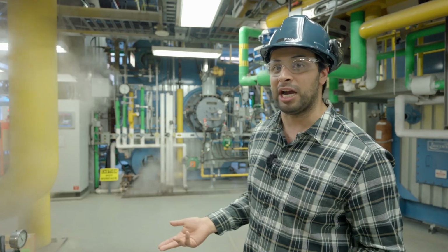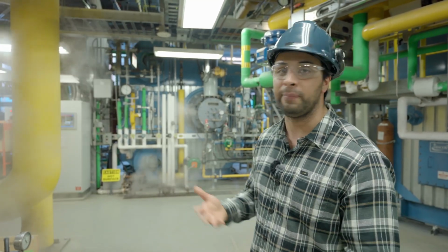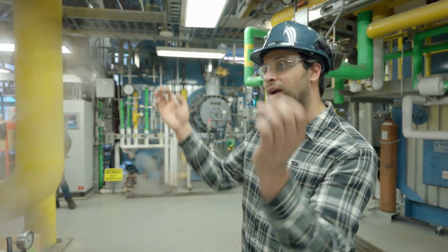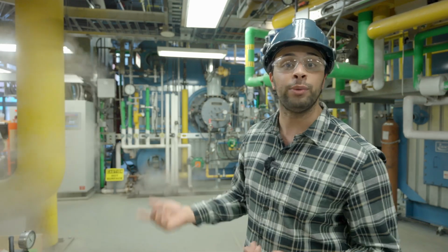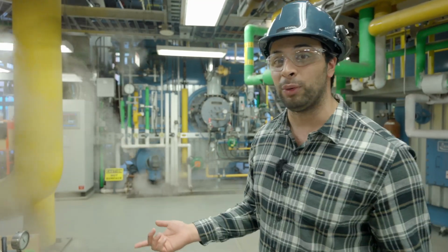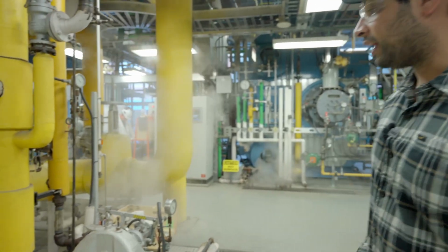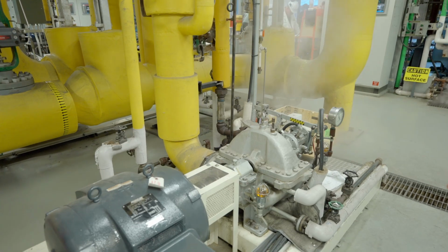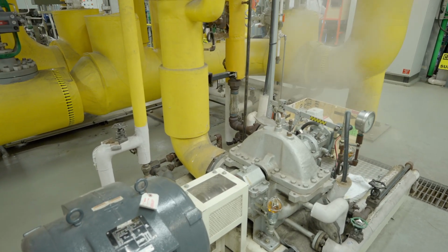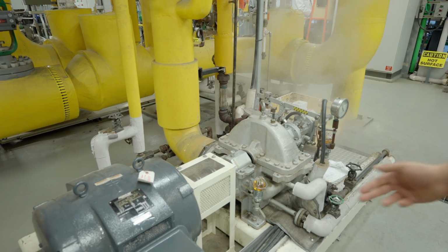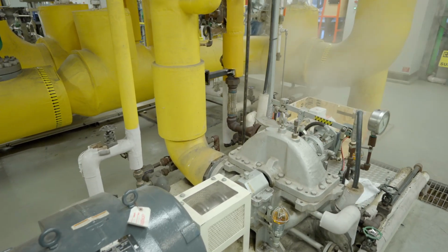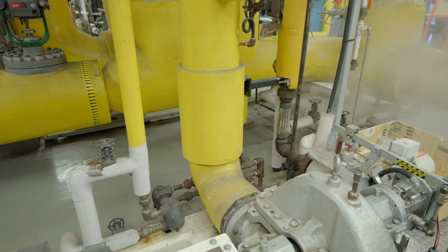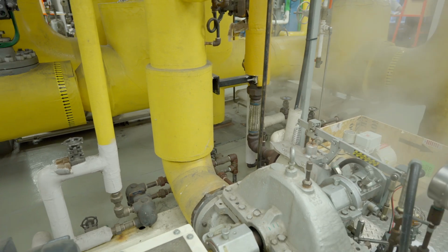If we were to just let the steam traps do their work from the beginning, it's possible that they wouldn't be able to keep up with the amount of condensate coming through, because, again, the steam's going to hit the cold pipes and flash into condensate. So that's what we do right from the beginning. And a similar principle applies when we're starting up the turbine here, that's why we have the bypass valve. As the components are heating up, we can just let all the condensate flow out into the drains while everything's getting nice and warm. And then once the shaft starts spinning and we've actually got movement, we can close those off, and the steam traps will do their job effectively, because we're not risking any cold pipes turning everything back into condensate.